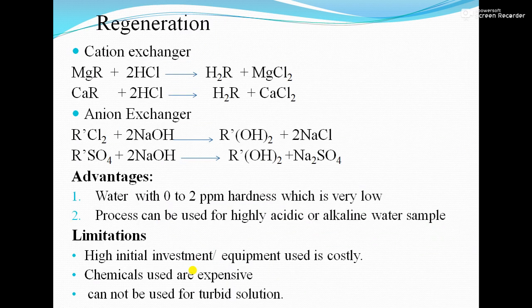Advantages: water with 0 to 2 ppm hardness, which is very low, can be obtained from this method. Second, the process can be used for highly acidic or alkaline water. Limitations: high initial investment — the equipment used is costly. Next, the chemicals used are expensive. Third, it cannot be used for turbid solutions. Those are the limitations of the ion exchange process.